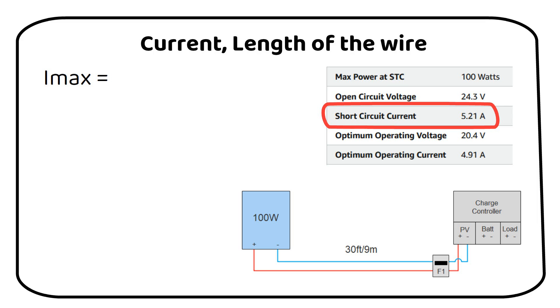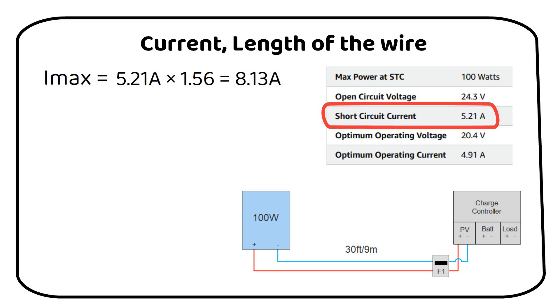So, our calculation for the maximum current, or Imax, through the wire is 5.21 amps times 1.56 equals 8.13 amps. This is the highest possible current that will flow through the wire.